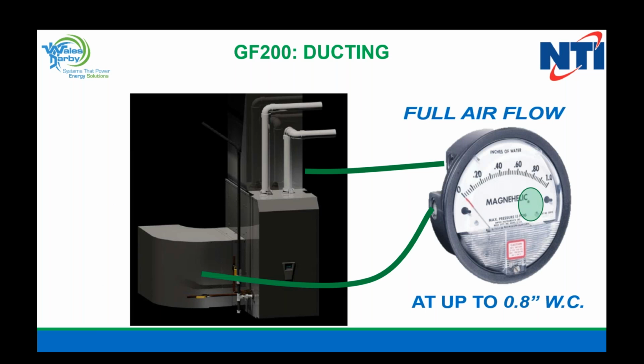So we do have the ability to support up to 0.8 inches of water column. So no different than you would see with your typical furnace. So no reason to shy away if it's a typical furnace install and they either have or do not have air conditioning and the hot water heater is aging out. Again, this is a viable option for a job like that.